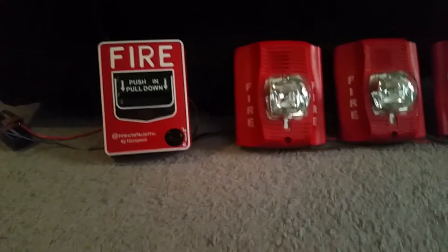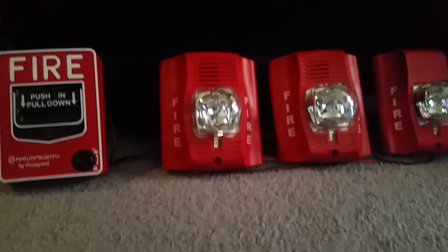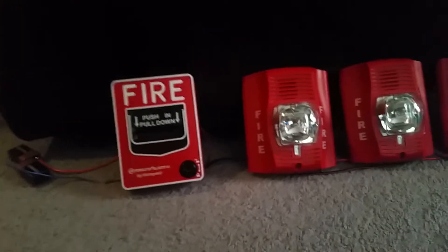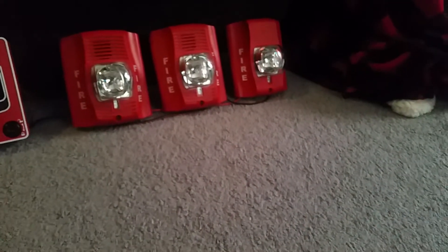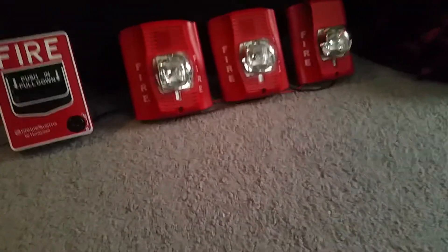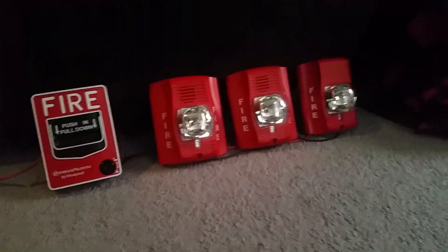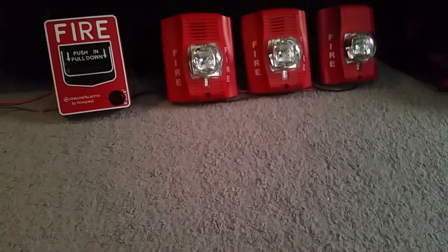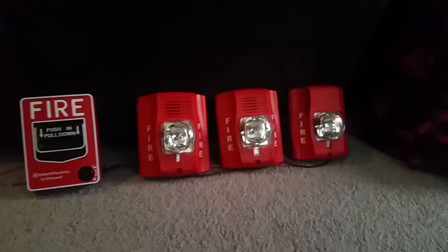They are pretty common and this is a very popular combo — you see them almost everywhere, same as SpectrAlert Classics, which are located almost everywhere still. The light to my left is turned on because it is kind of dark outside. Also be aware that these three strobes are going to sync for a while because they're all connected on one circuit from the batteries. They sync with each other without a sync module — I'm not sure why, it just does. All the strobes are set for 15 candela.